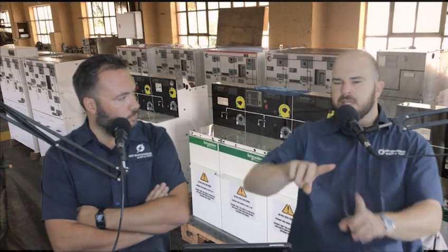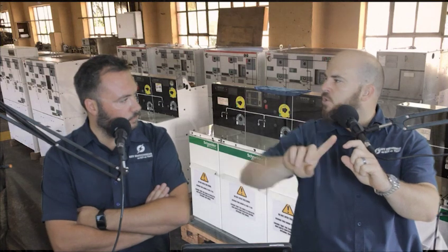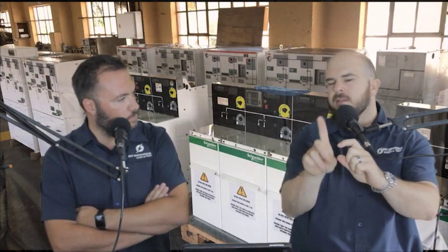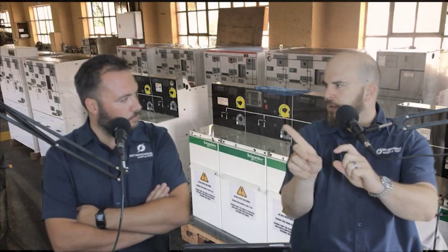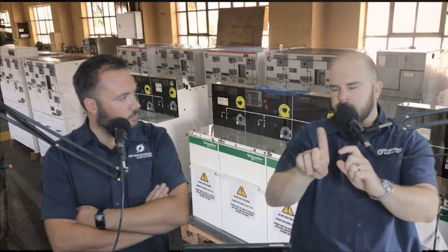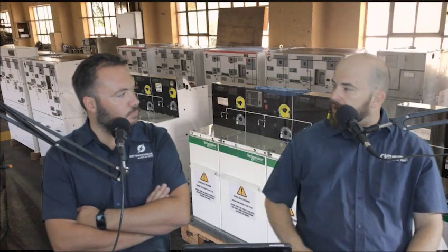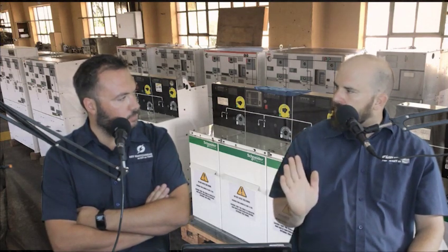A lot of people see a long green bar and a small red bar on the gauge, and they think you should always be full, almost like a tank of petrol, but it's not like that. There's a design level. If temperature increases, it can go up a little bit. If height above sea level increases, it can go up a bit. But you don't want it to be at the higher end of the green. You just want it above the red. That's the safe level.